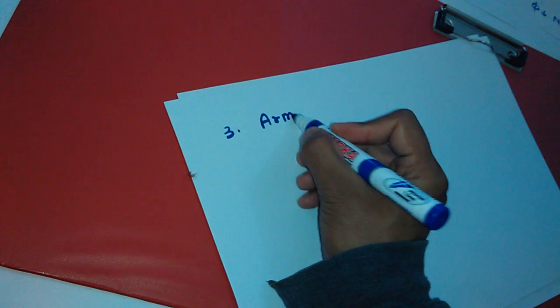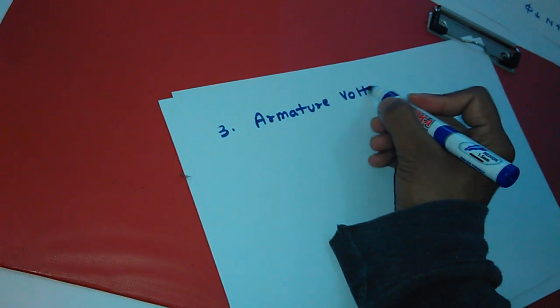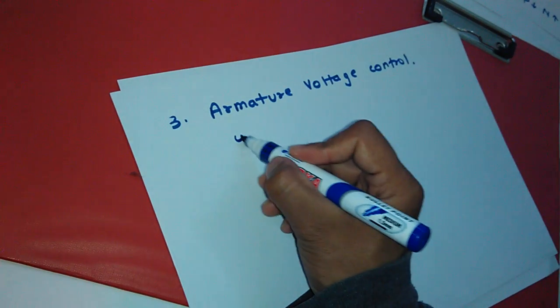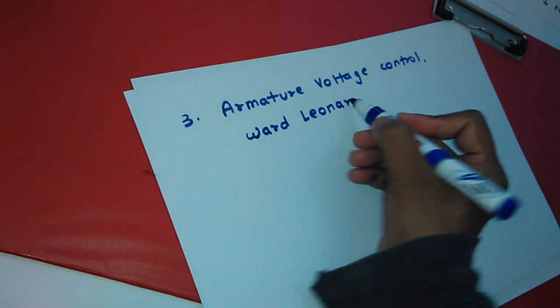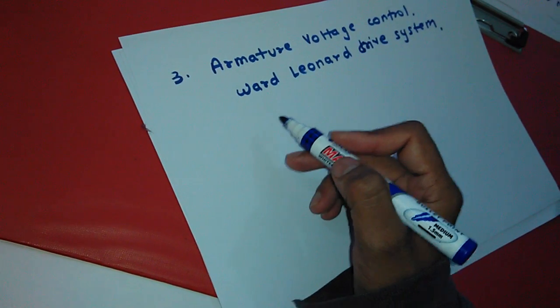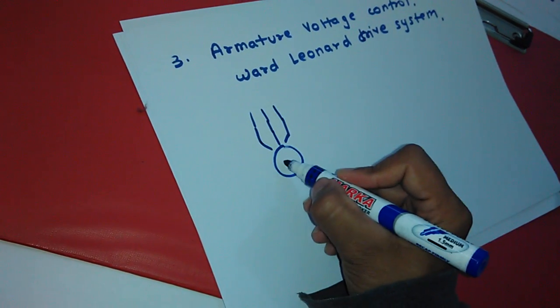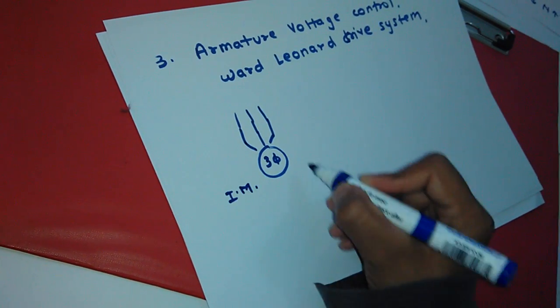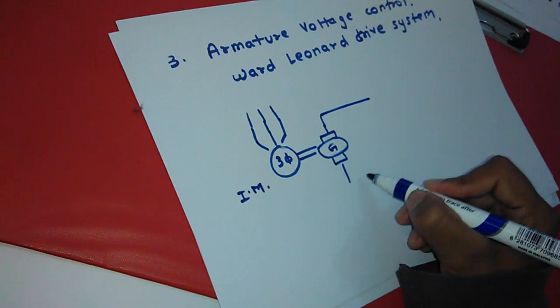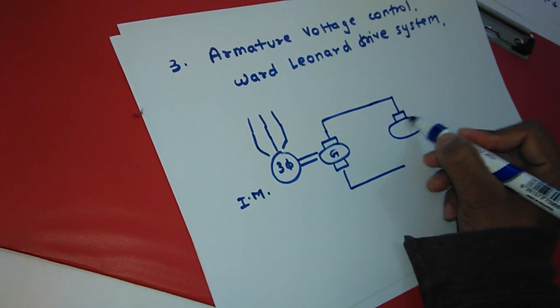The third method is armature voltage control. From this method, the supply voltage can be changed so that speed will be changed. This is done by using the Ward Leonard drive system. For this we require a motor-generator set to control the speed of the motor. A three-phase induction motor is coupled to a DC generator, and that DC generator is again connected directly to the motor whose speed control we need.